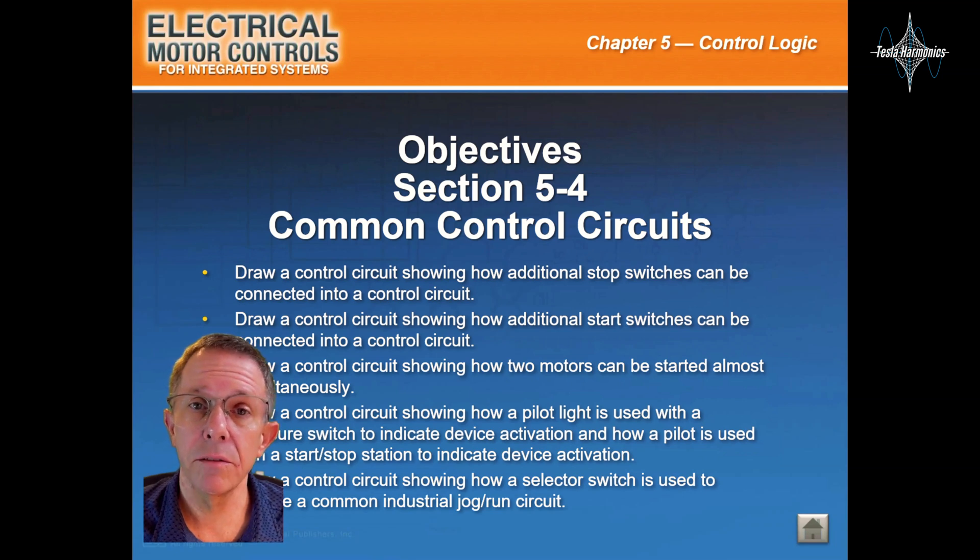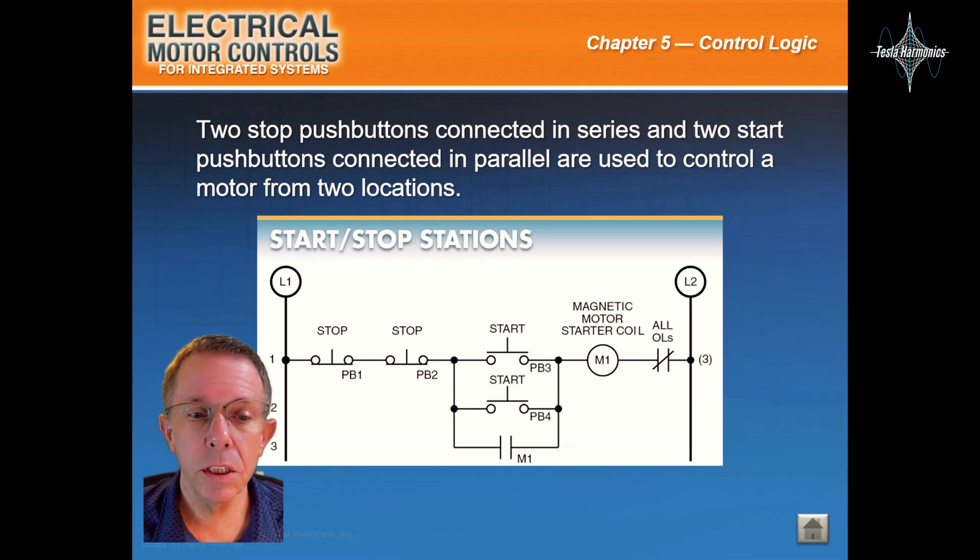This will be section 5-4, common control circuits. Two STOP buttons connected in series and two START buttons connected in parallel are used to control motors from two locations.